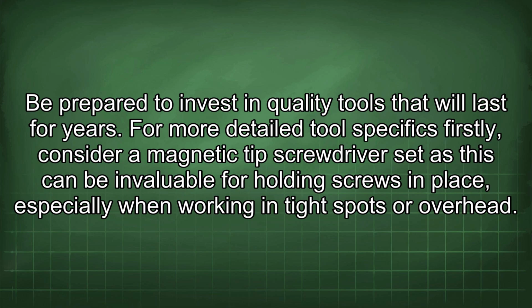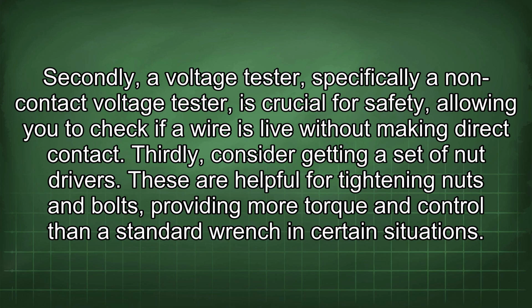For more detailed tool specifics, firstly, consider a magnetic tipped screwdriver set, as this can be invaluable for holding screws in place, especially when working in tight spots or overhead. Secondly, a voltage tester, specifically a non-contact voltage tester, is crucial for safety, allowing you to check if a wire is live without making direct contact.